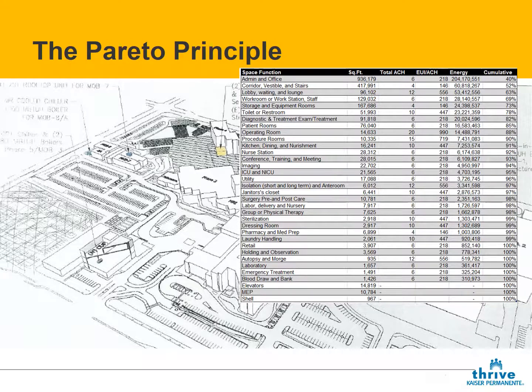And what it takes is time and care. What I'm having my engineers do now is, every time we do an air handler project, we look at all the rooms, and you need to maximize those VAV opportunities at every room, unoccupied turndowns, and what the real minimums are that you need in that space. It takes that room-by-room level. Stop thinking of air in terms of cubic feet per minute and start thinking of air in terms of cubic feet per year. And once you make that transition, then it's like, okay, I get it.